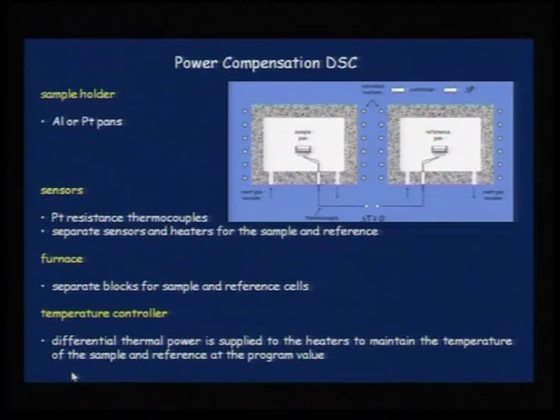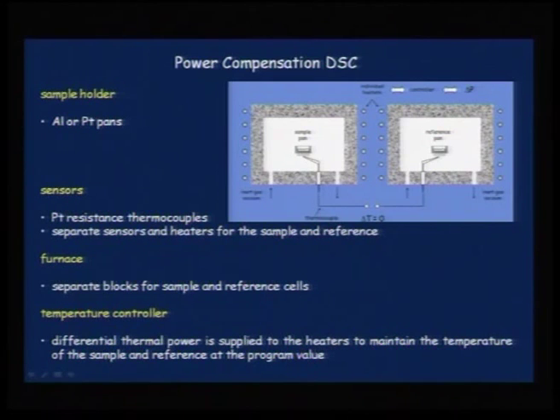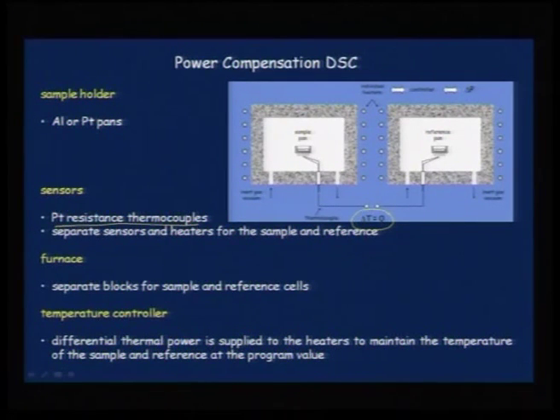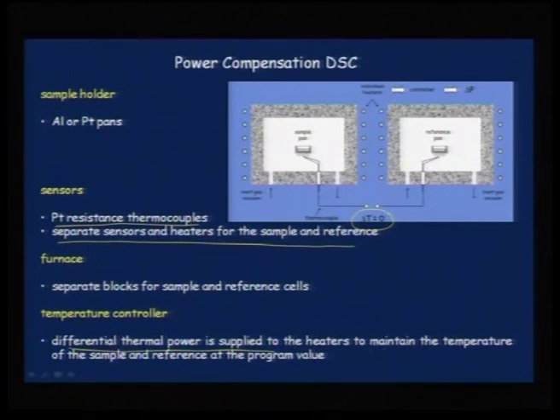There are two ways to achieve DSC: using a power compensation method or a heat flux method. In the power compensation method, you have two different alumina blocks to heat the pans — one for the sample and one for the reference — connected to thermocouples where delta T is maintained at zero. Separate sensors and heaters are used, and differential thermal power is supplied to the heaters to maintain the temperature of sample and reference at the programmed value.